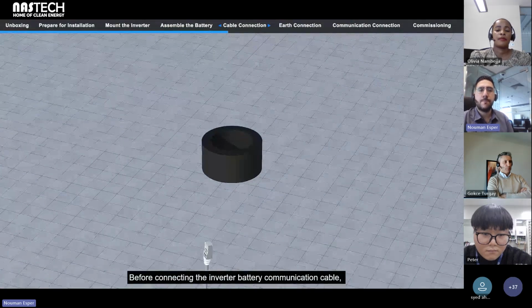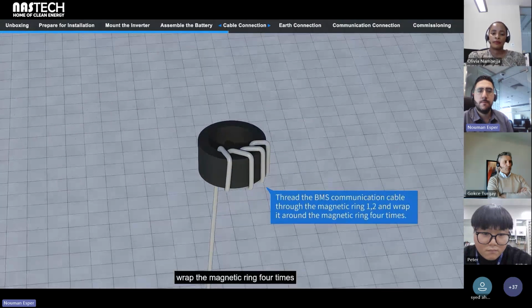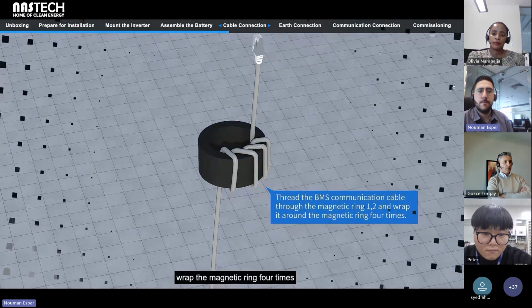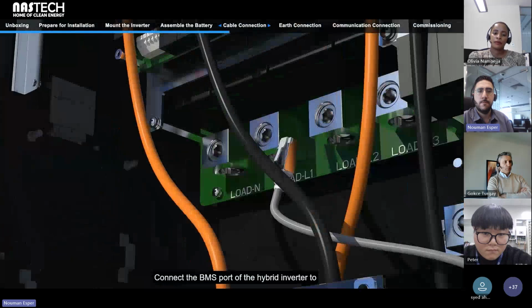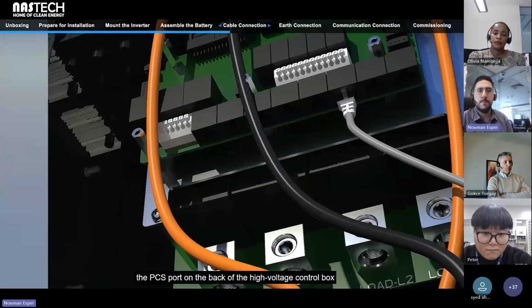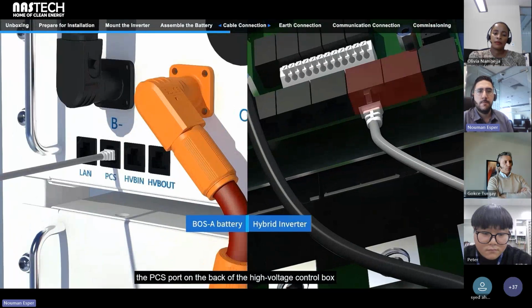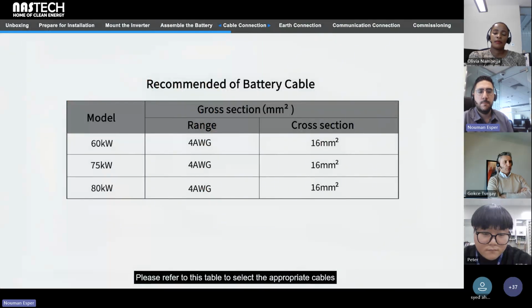Before connecting the inverter battery communication cable, wrap the magnetic ring 4 times. Connect the BMS port of the hybrid inverter to the PC's port on the back of the high voltage control box. Please refer to this table to select the appropriate cables.